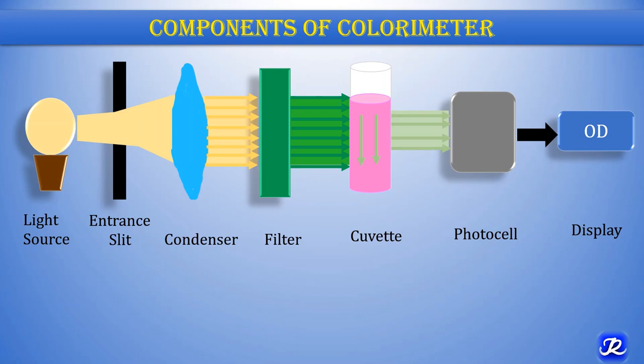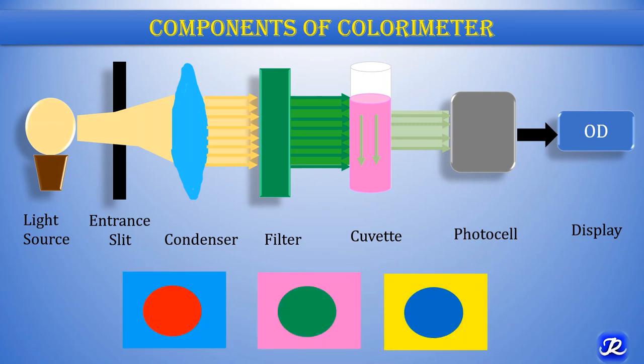An important question is why we use complementary color filters. In this picture, a green color filter is used for a solution having purple color — these two are complementary colors. The aim of using a complementary color filter is to facilitate maximum absorption. So when using a colorimeter, depending on the color of the solution, we adjust the filter accordingly. For example, for a light blue color, a red filter is used; for purple, a green filter is used; for yellow, a blue filter is used. Using the complementary color facilitates maximum absorption and allows us to obtain the OD.